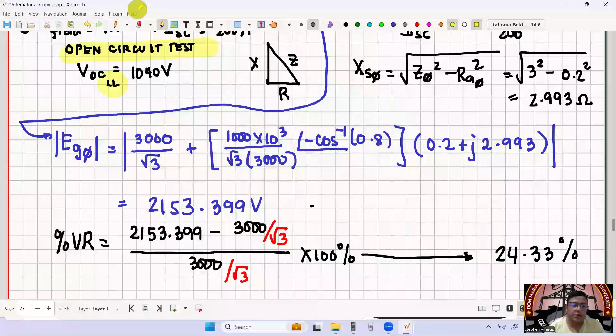So next, number 28. A 25 kVA alternator has a total loss of 2,000 watts. So P loss is equal to 2,000 watts when it delivers rated kVA to a load at a power factor of 0.76. Take note, our SFL here, which we haven't placed yet, is 25 kVA.